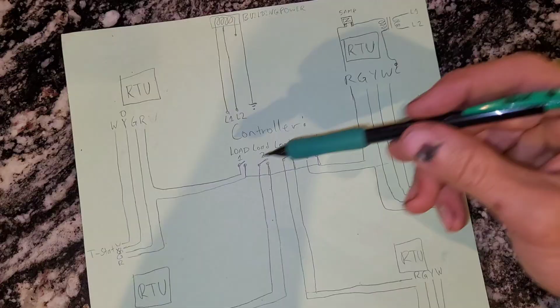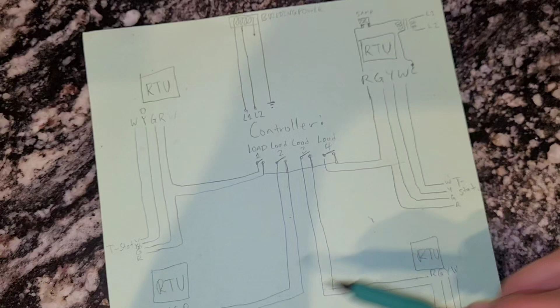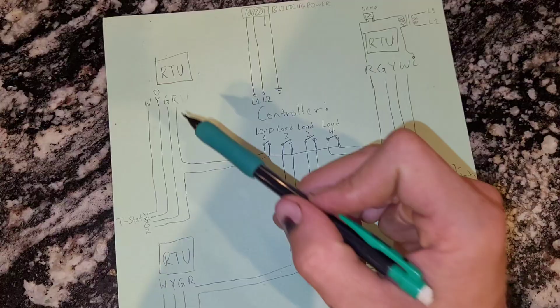going across to all of these, which meant when they hooked everything up, the 24 volts from all the rooftop units were fighting each other, and this rooftop unit actually must have had a slightly stronger fuse or something, and so it burnt the fuse in this one and in this one, which is what we saw when we were up there.